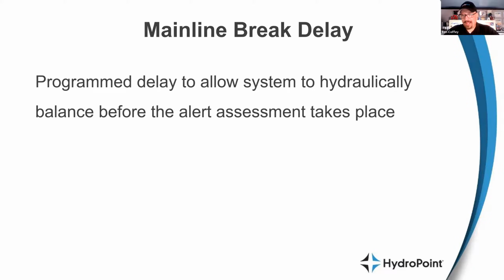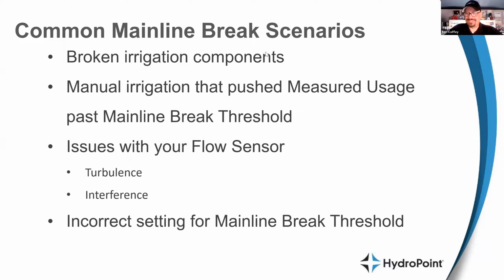Definitely something to keep an eye on is if you know you have an older system like the ones that we find on Eric's HOAs, sometimes we have to adjust this delay because the valves are so slow that it's causing false alerts, right? You get stuck in a pattern of chasing alerts that aren't really alerts because the system isn't fast enough to beat the delay. So WeatherTRAK comes with a 3-minute default, but you can bump that up to as much as 6 minutes on an alert.